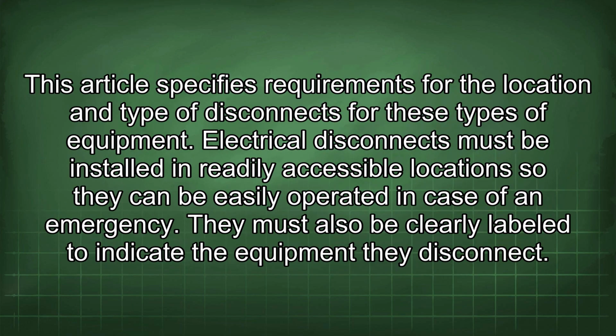This article specifies requirements for the location and type of disconnects for these types of equipment. Electrical disconnects must be installed in readily accessible locations so they can be easily operated in case of an emergency. They must also be clearly labeled to indicate the equipment they disconnect.